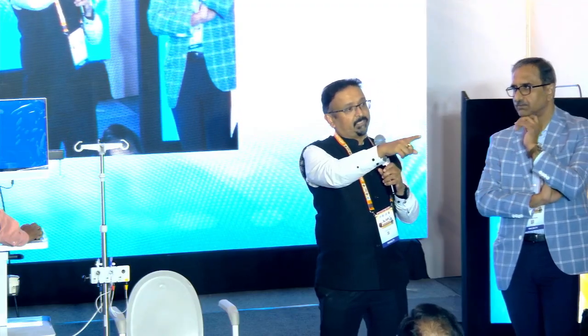Then the rectal catheter has a rectal balloon and another lumen, which is to inflate your balloon if needed. That is again an optional thing, because sometimes if the rectal balloon is overfilled, you will have a negative deflection in the detrusor pressure, because the rectal pressure is more than the vesical pressure. Then the detrusor pressure will start at minus, and if you zero it at that point, the detrusor pressure is running below the floor. So you won't know, it probably has come already up to here because you started at minus and zeroed it at minus. That is when things go wrong.